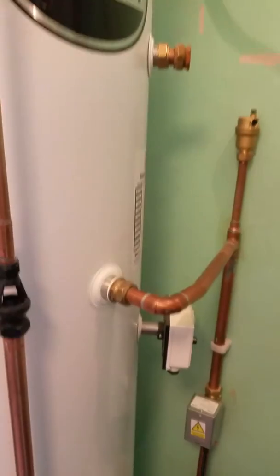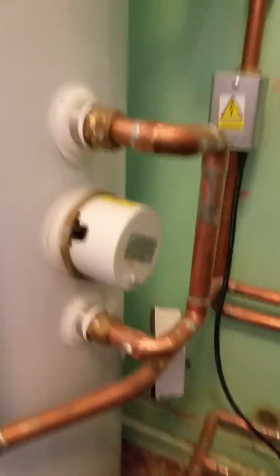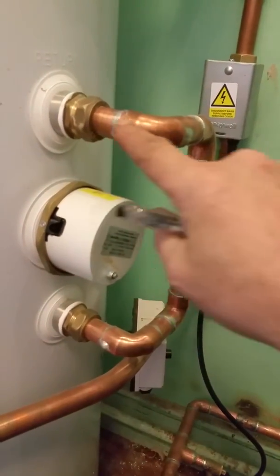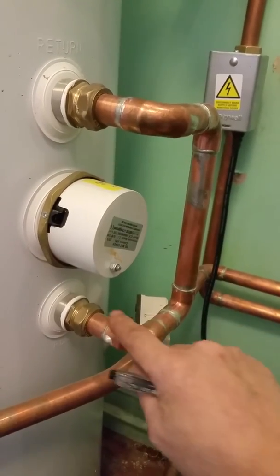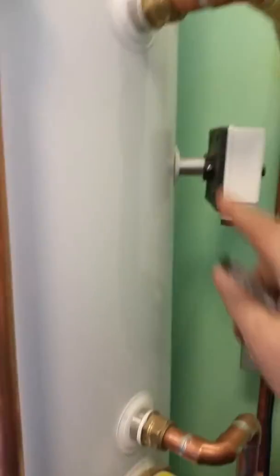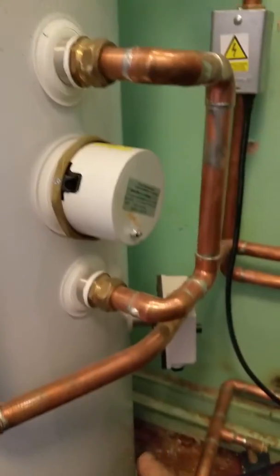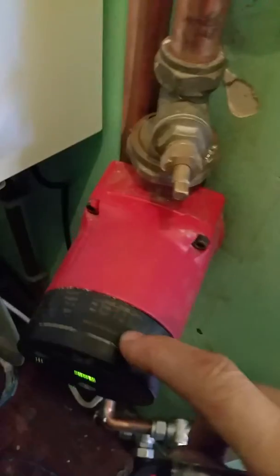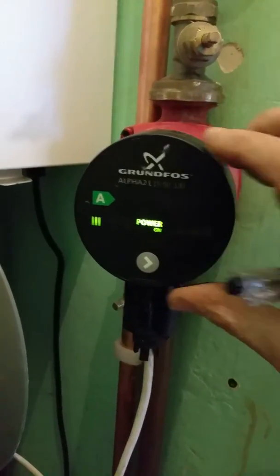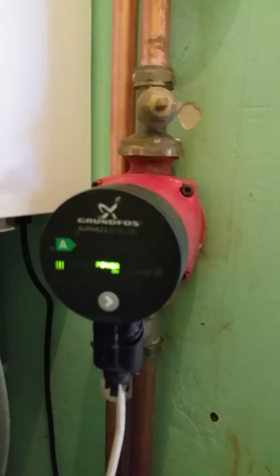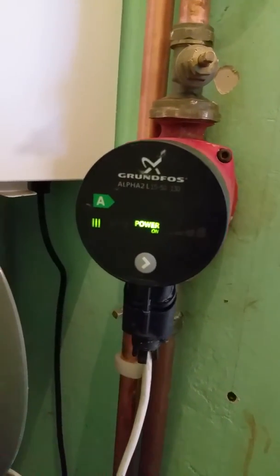I can't even get it to run through this solar cylinder, which I didn't do this again, as I say, but the guy was instructed to do it in series and not in parallel. So he's not only got the resistance of the first coil, but the resistance of a second coil, and there's just no way that this pump can cope with that. So the cure for this is either a bigger pump, which I think would have to be a 7 or 8 meter head pump, which is crazy on an 18 kilowatt boiler. Imagine coming in and seeing a 7 or 8 meter head pump.